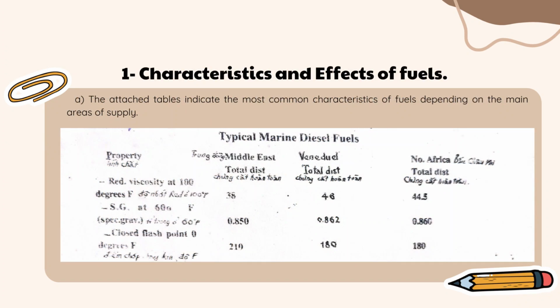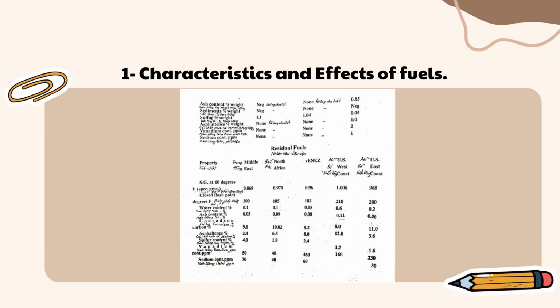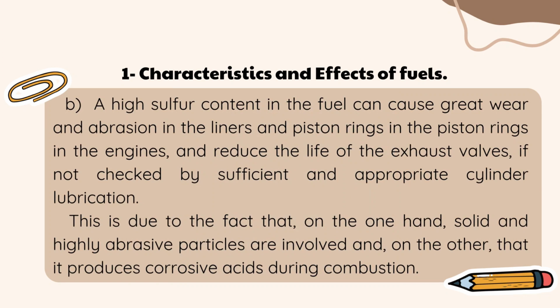1. Characteristics and effects of fuels. A. The attached tables indicate the most common characteristics of fuels depending on the main areas of supply. B. A high sulfur content in the fuel can cause great wear and abrasion in the liners and piston rings in the engines, and reduce the life of the exhaust valves, if not checked by sufficient and appropriate cylinder lubrication. This is due to the fact that, on the one hand, solid and highly abrasive particles are involved and, on the other, that it produces corrosive acids during combustion.